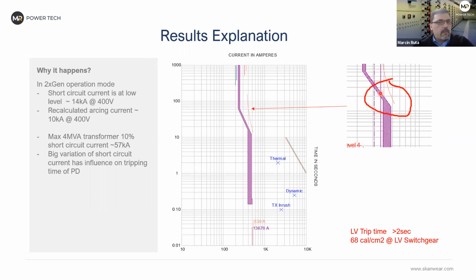So that was a very low number. And if you can see here, what I highlighted, the breaker had a problem tripping at all. It will not detect this. And the time was not even 2 seconds, it was more than 20 seconds. But just as in NFPA, we use 2 seconds to stop at this specific project. And the maximum we can expect was 57 kiloamps.